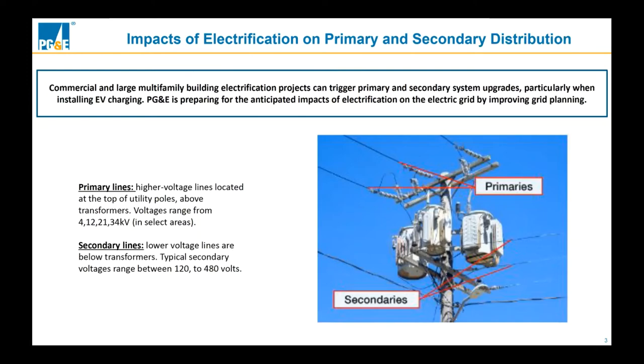Those lines operate as low as 4 kV, or 4,000 volts, going up to 12 kV, 21 kV, and the highest we have in our service territory is 34.5 kV. The most common of this voltage class is probably 12 kV in PG&E service territory, and the least common is the largest, 34.5 kV. San Francisco is the only city where they receive primary distribution at 34.5. And for the lowest, 4 kV, there are some areas in PG&E service territory served by 4 kV primary distribution, like downtown San Jose, as an example.